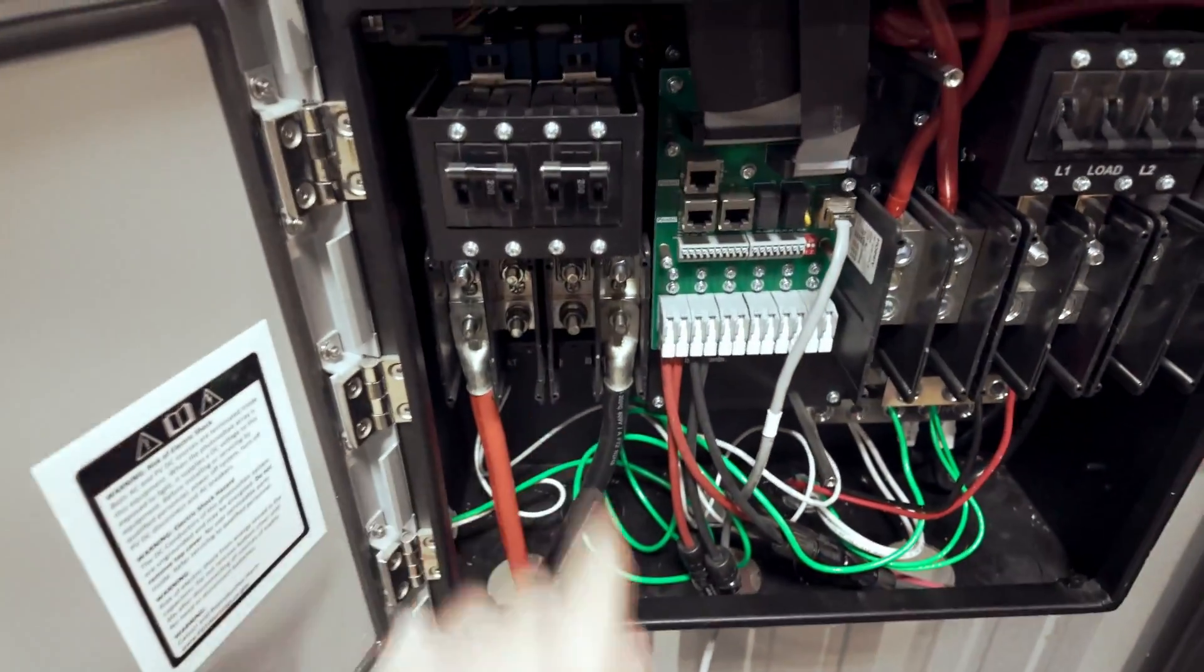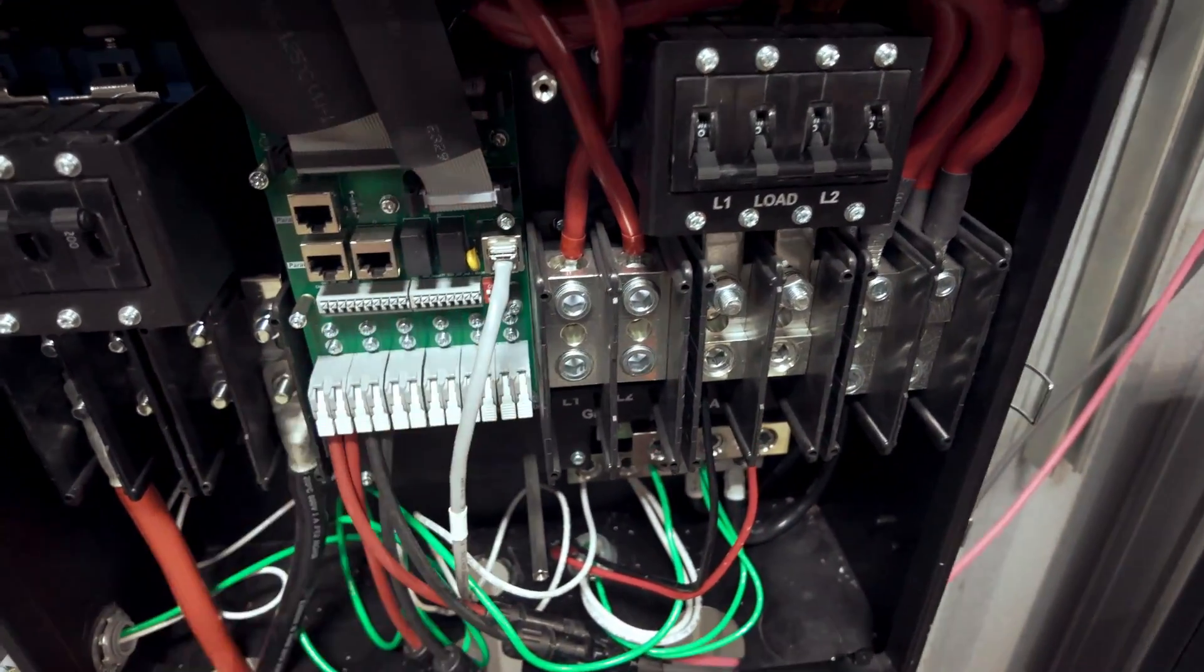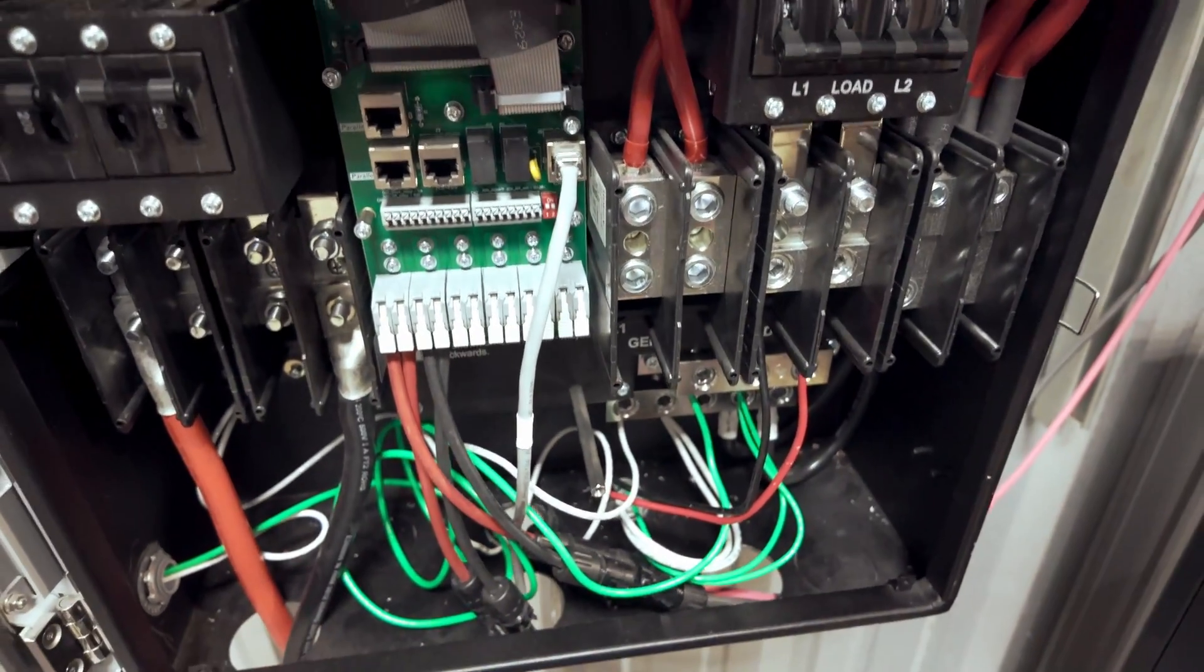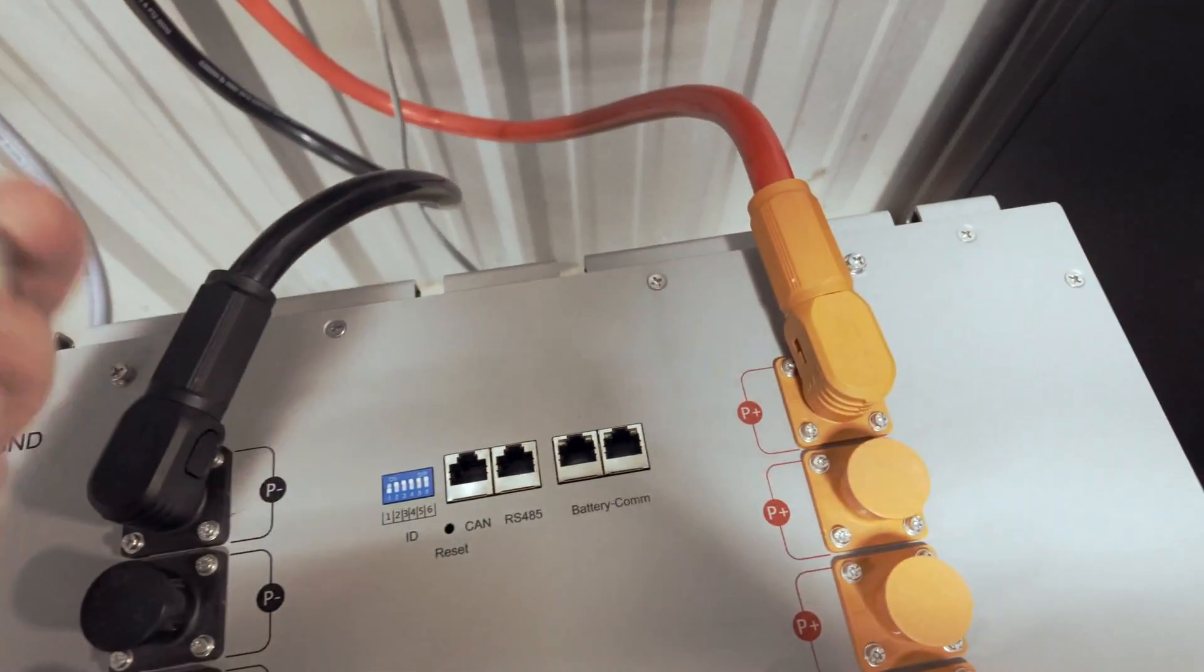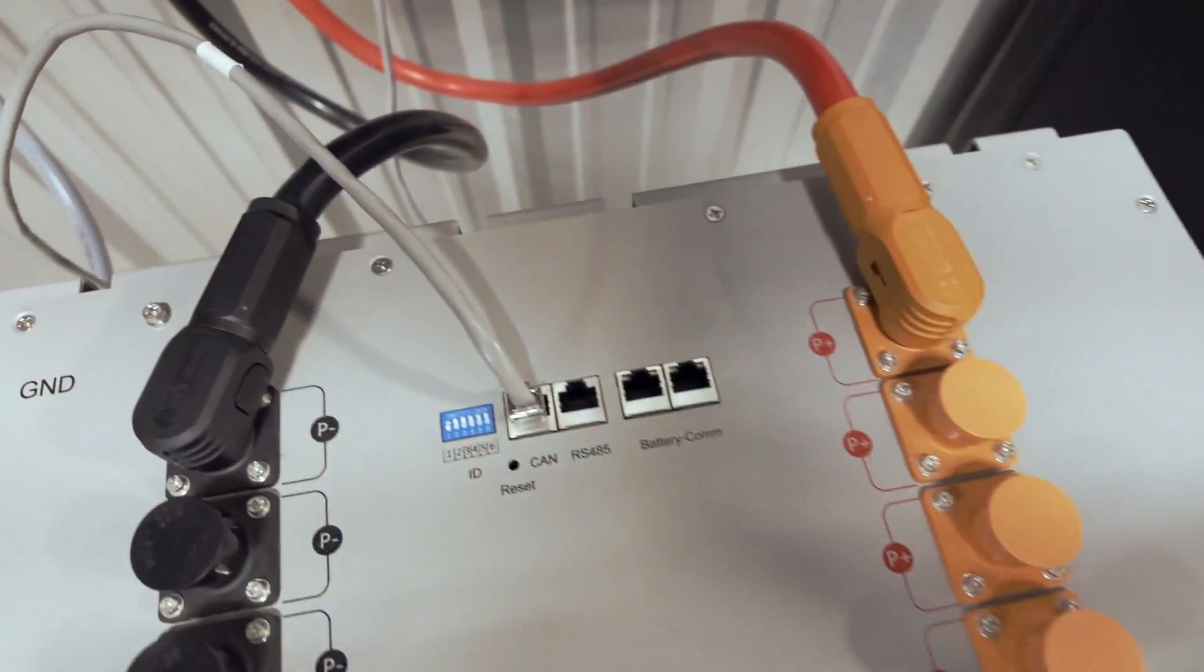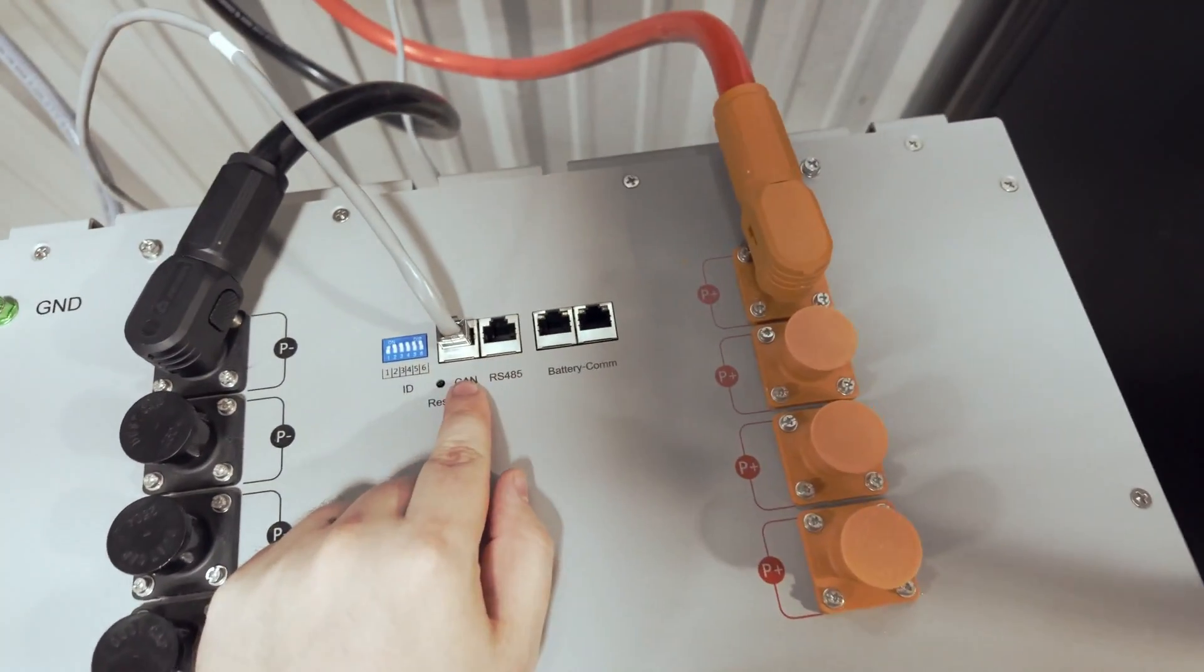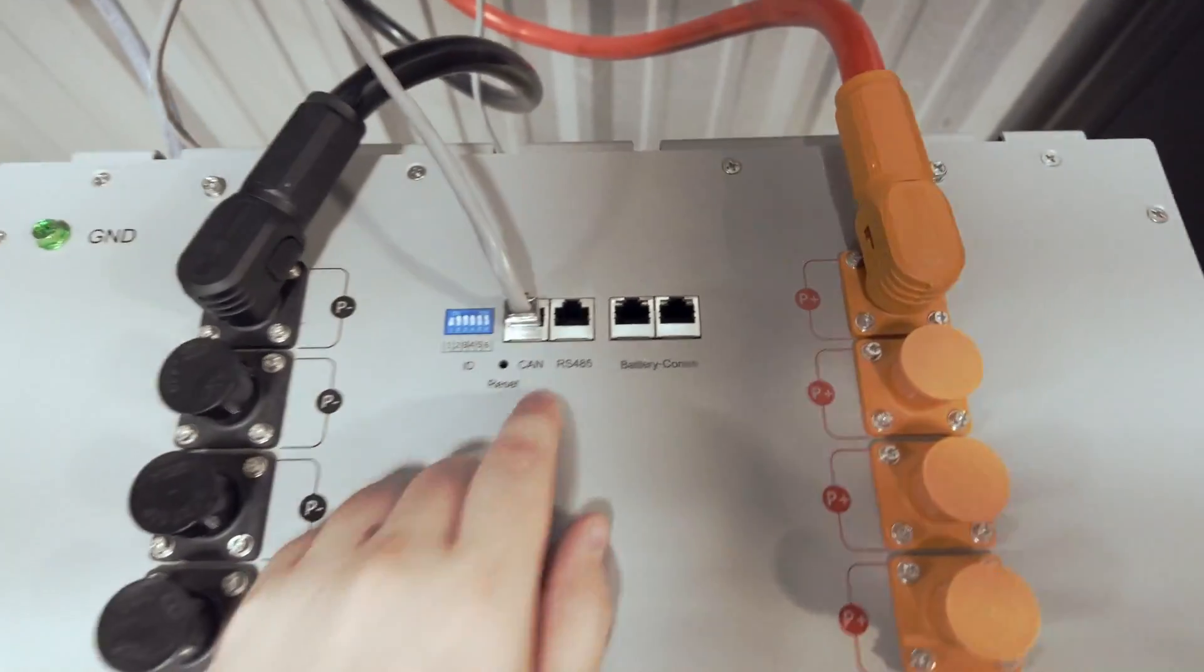This will provide power to the Solark and then you will need to plug in a straight through pinned communication cable from the CAN bus on the Solark to the CAN port on your EG4 battery. Now do note the LifePower4 does not have a CAN port. You will need to use the communication hub for this feature.